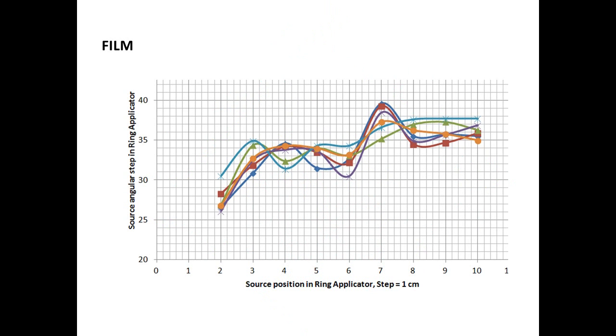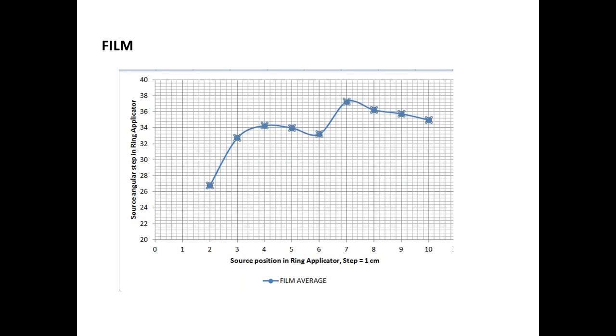Source angular steps measured on different dates in different source guide catheter positions are collected on this figure. The family of curves reflects the accuracy level of the measurement and the snaking nature of the source cable. Here is the average film source angular steps curve.